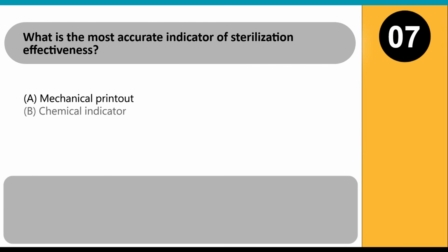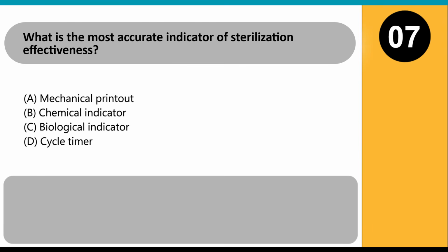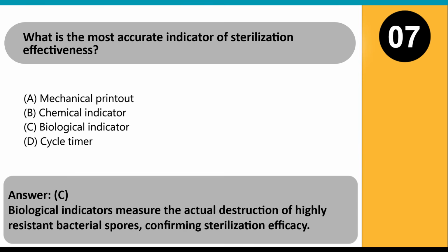What is the most accurate indicator of sterilization effectiveness? A. Mechanical printout. B. Chemical indicator. C. Biological indicator. D. Cycle timer. Answer C. Biological indicators measure the actual destruction of highly resistant bacterial spores, confirming sterilization efficacy.